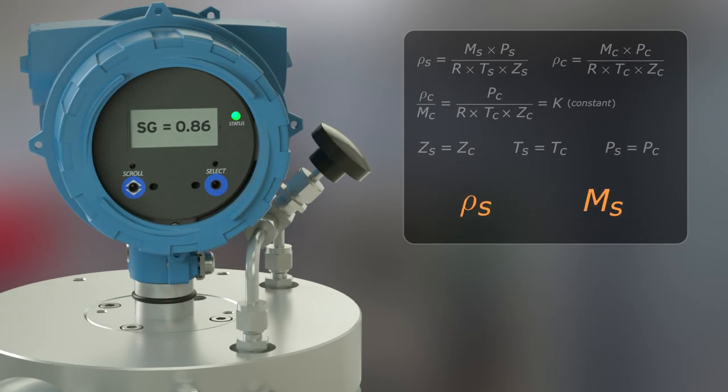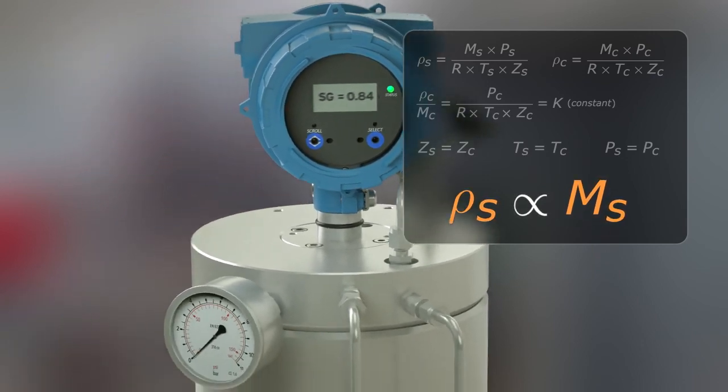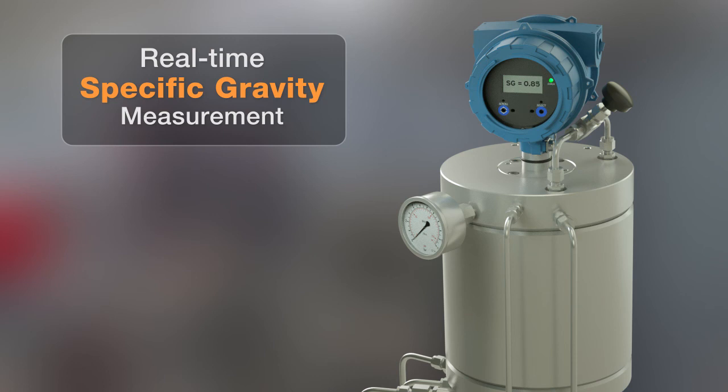As a result, only changes in gas composition will cause a change in the measurement of the sensor, and a continuous flow through the meter is able to provide a real-time specific gravity measurement with an accuracy up to 0.1%.